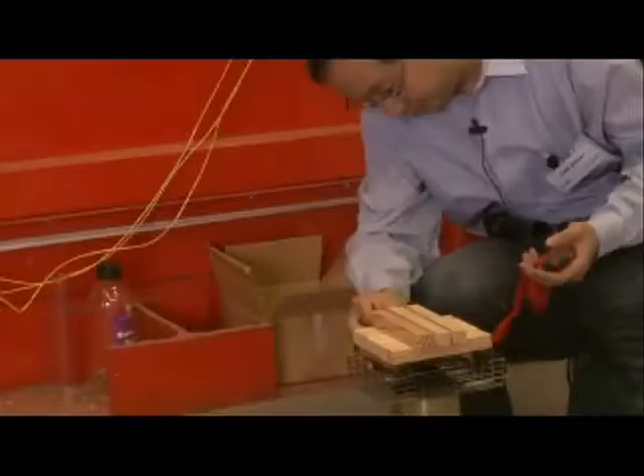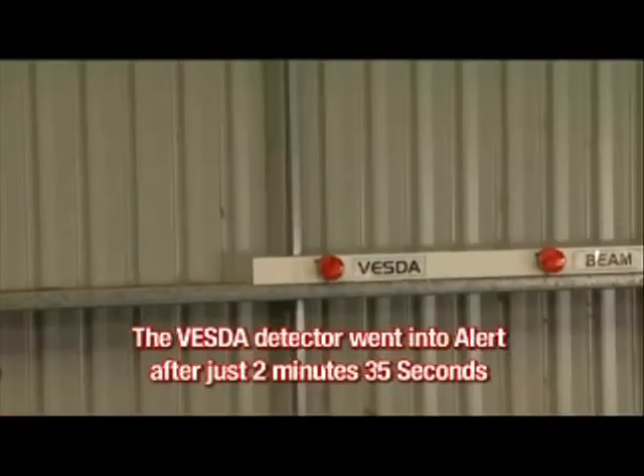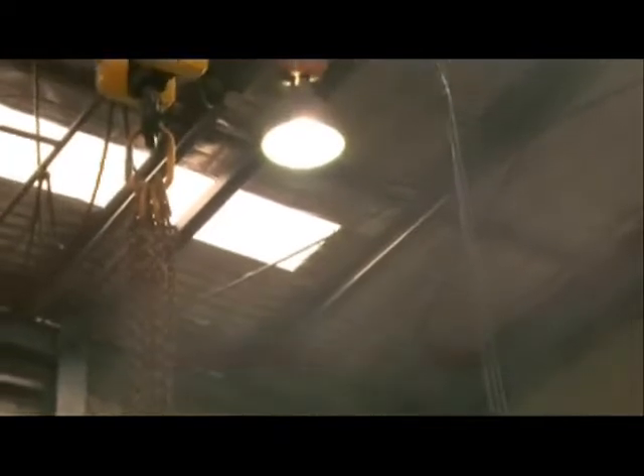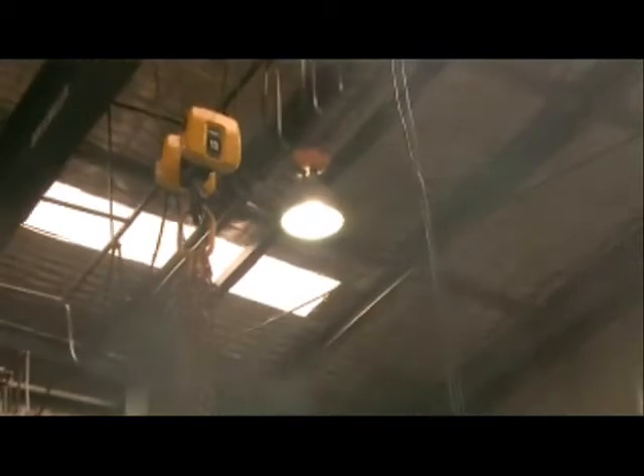Next, the warehouse doors were opened and the same test repeated. This time, the VESDA detector went into alert after just two minutes thirty-five seconds, and then to fire one in five minutes. Once again, the VESDA proves superior as the remaining two detectors have still not registered a reading.